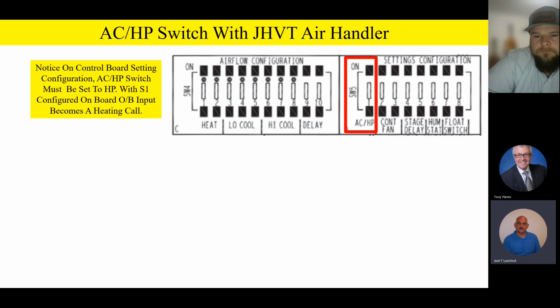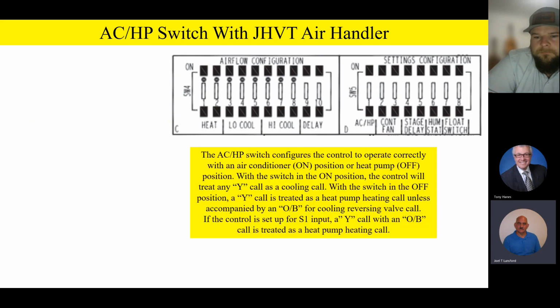So let me stress this one more time, that AC/heat pump switch has to be in the HP or heat pump position. Here's a little bit more of an explanation as well. That switch configures the control board to operate correctly with an air conditioner when it's in the on position, or a heat pump when it's in the down or off position. With the switch in the on position, let's say you're on a straight cooling unit, the control will treat any Y call as strictly a cooling call. However, with the switch in the off position, a Y call is treated as a heat pump heating call unless you have an O/B for cooling reversing valve.